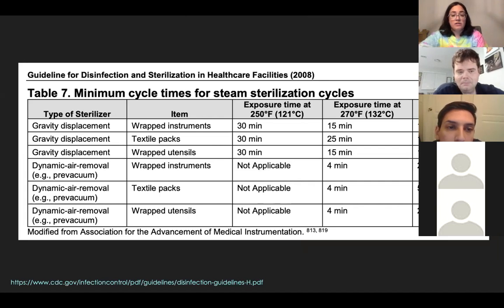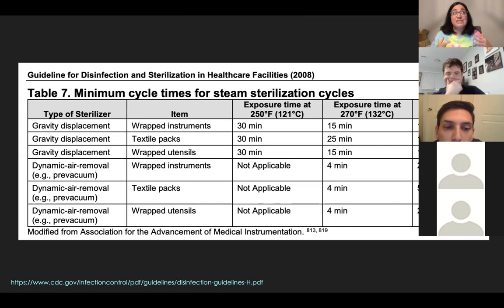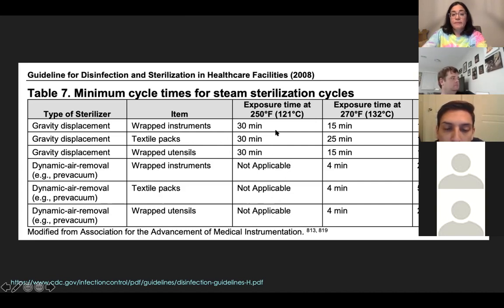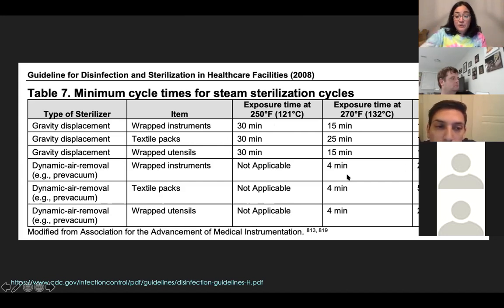Minimum cycle times for steam sterilization come from the CDC document, which I highly recommend reading. Knowing your resources is really important as an infection preventionist. Gravity displacement sterilizers use a lower temperature — around 250°F — which is not applicable for dynamic air removal sterilizers. You don't need to memorize the specific times, but you need to know where to find this information. I didn't memorize it — I just know exactly where to go.